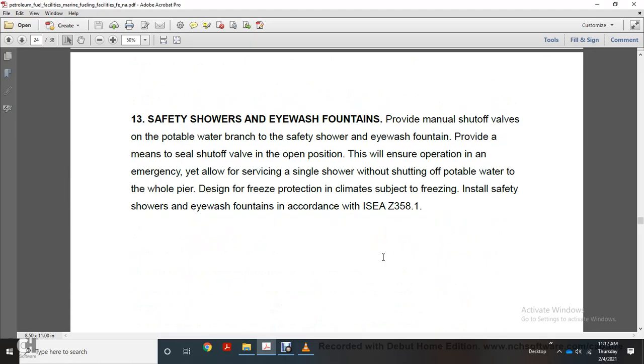13. Safety showers and eye wash fountains. Provide a manual shut-off valve with a potable water branch for the safety shower and eye wash fountain. Provide a means of safety sealing the shut-off valve in the open position to ensure operation in an emergency. This allows servicing the shower without shutting off the potable water to the whole pier. Design freezing protection in climates subject to freezing. Install safety showers and eye wash fountains in accordance with ISEA Z358.1.